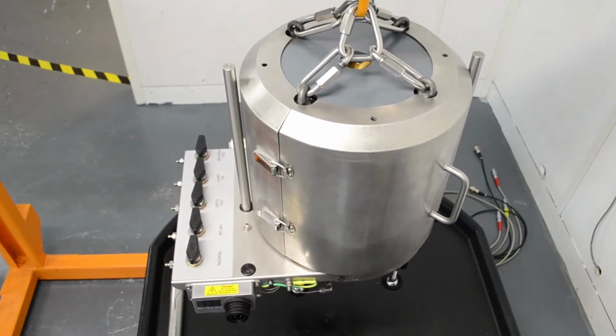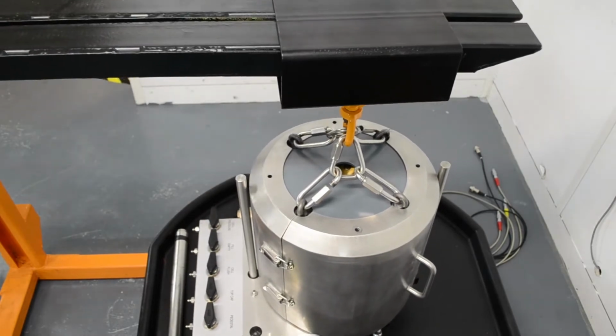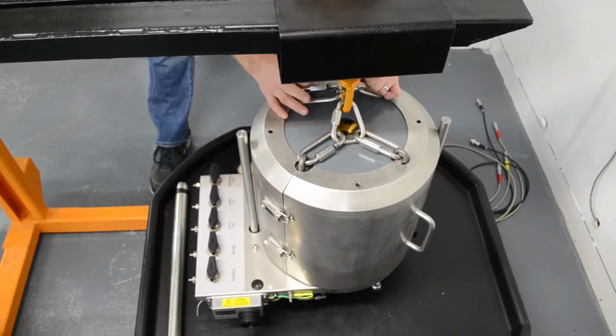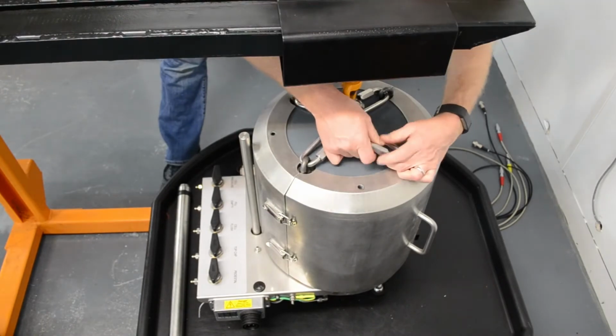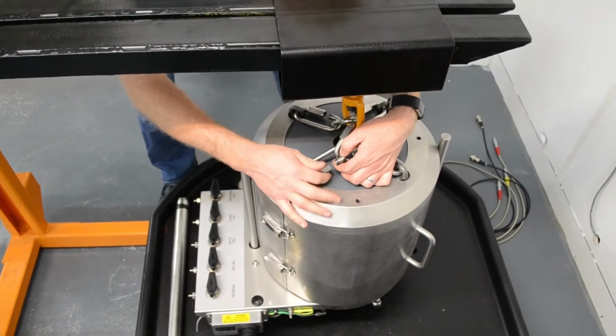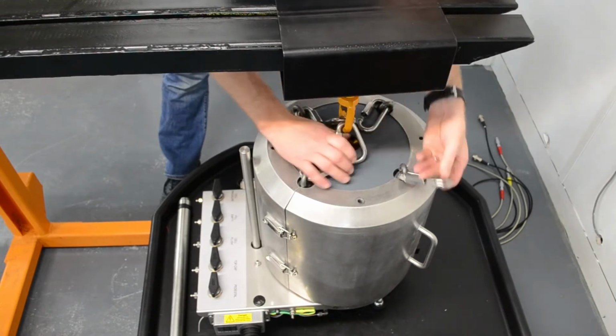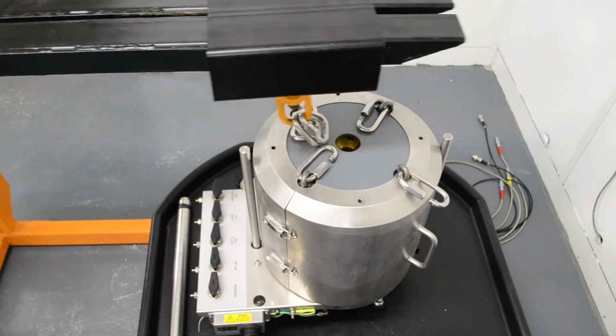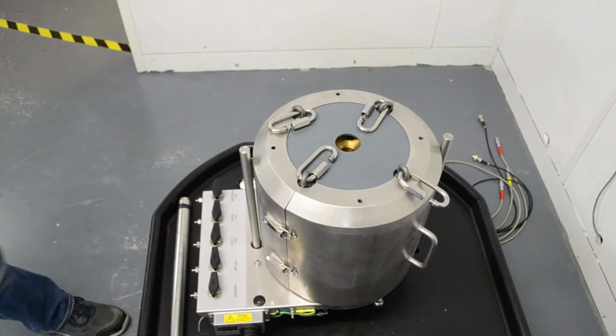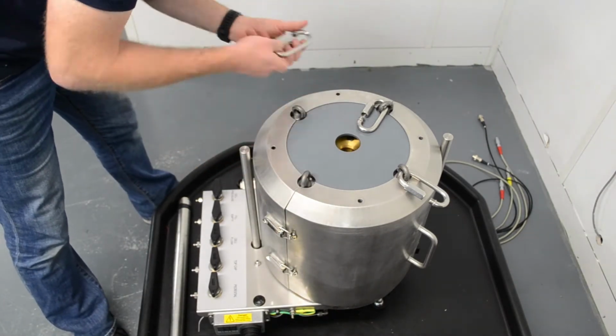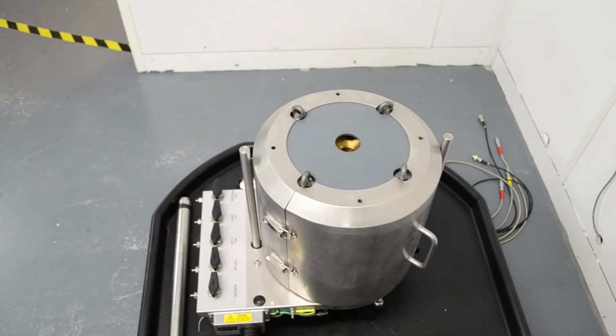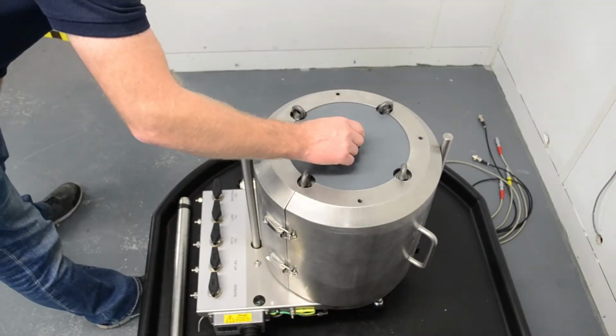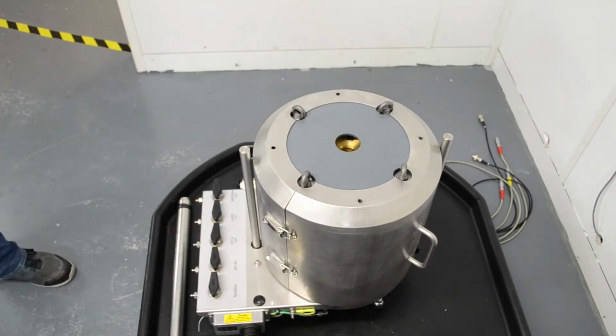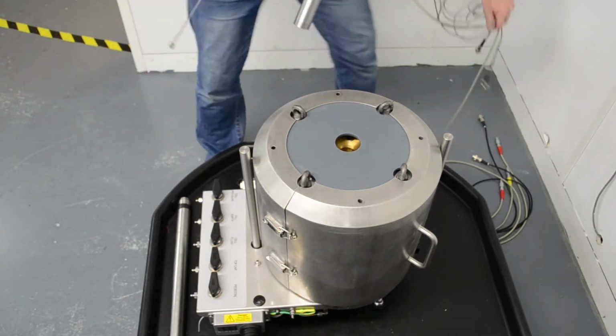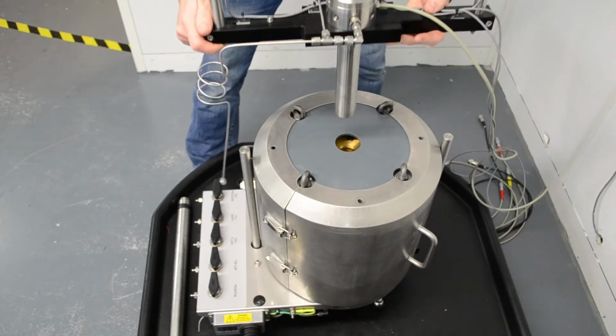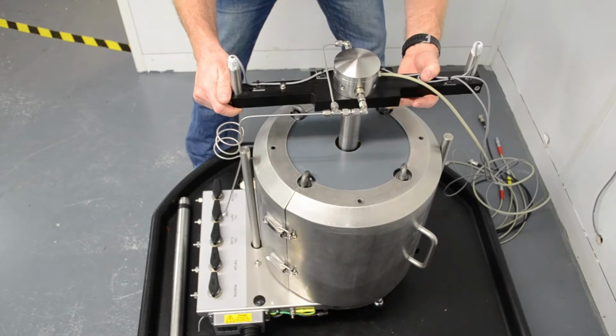Lower the cell assembly back down. Remove the lifting points to allow placement of the Topcap assembly. Place a sample inside the cell. Lower the Topcap assembly into place. Connect the saturation line if required. Center the axial displacement transducers if fitted.